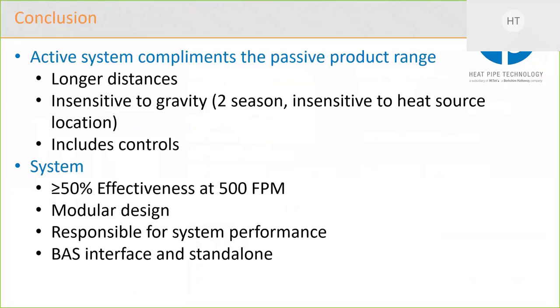The system has a greater or equal to 50% effectiveness at 500 feet per minute. Now that's sensible effectiveness, but that is particularly useful when meeting code for labs. It's a modular design so that we can provide selections relatively quickly and also at an economical cost. We're responsible for the whole system. So remember I said we make the coils and we make the skids. We're responsible for all of that. And also we have flexibility in the controls. It can interface with the BAS and it can stand alone and just operate itself without any interface to a BAS.